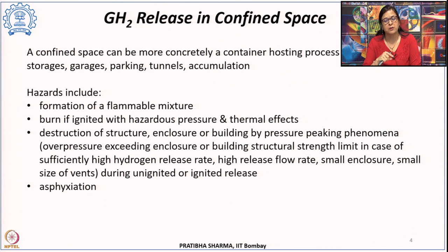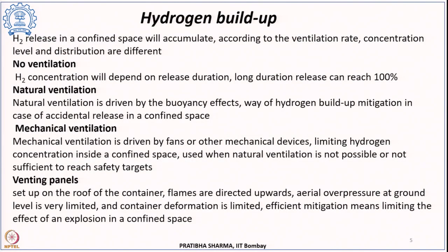However, this pressure peaking phenomenon is complicated, and it depends upon what the hydrogen release rate is, what the size of that enclosure is, and what the size of that vent is. So it depends upon many factors. Now let us say there is a release of gaseous hydrogen in a confined space, but there is no ignition source present nearby. In that case, it will displace air or reduce the oxygen concentration and can cause asphyxiation for the persons present in that enclosure or confined space.